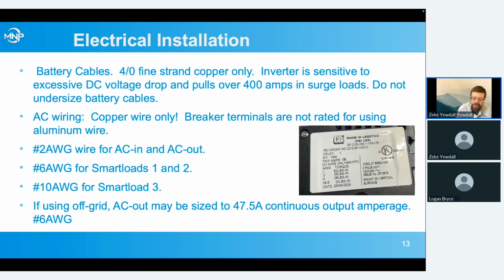So copper wire only. 2 gauge is what we recommend for AC in and AC out. 6 gauge for the smart loads and 10 gauge for the smaller smart load. If you're using it off grid and you're not using the AC in, you can size the AC out for the continuous output amperage of the inverter rather than the 100 amp transfer capacity. And that would be 47.5 amps continuous output, which translates to 6-gauge copper wire. If you're grid tied and you're using the full 100 amps, you need 2-gauge.